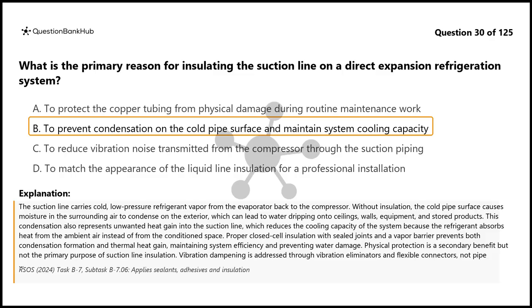Proper closed-cell insulation with sealed joints and a vapor barrier prevents both condensation formation and thermal heat gain, maintaining system efficiency and preventing water damage. Physical protection is a secondary benefit but not the primary purpose of suction line insulation. Vibration dampening is addressed through vibration eliminators and flexible connectors, not pipe insulation. Matching the appearance of the liquid line is not a technical requirement since liquid lines are not always insulated in standard direct expansion systems.